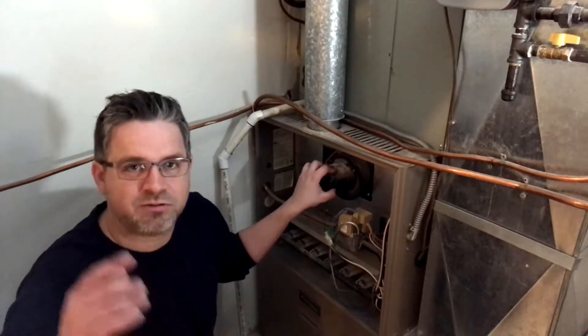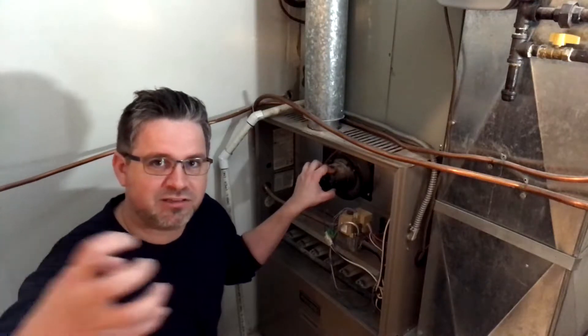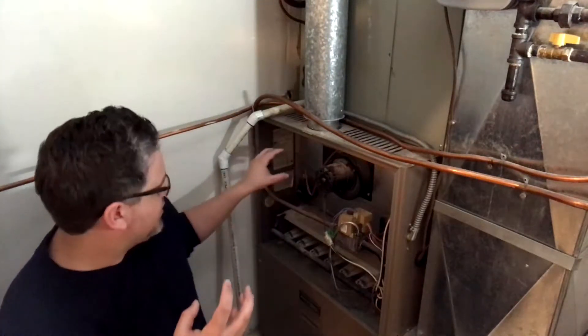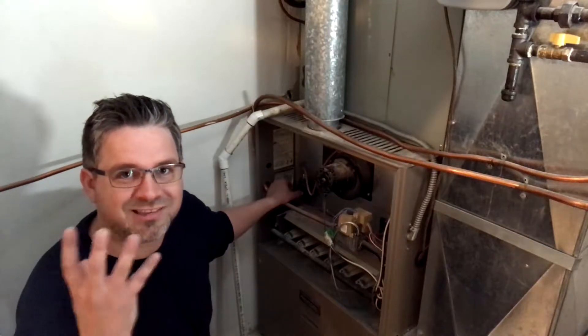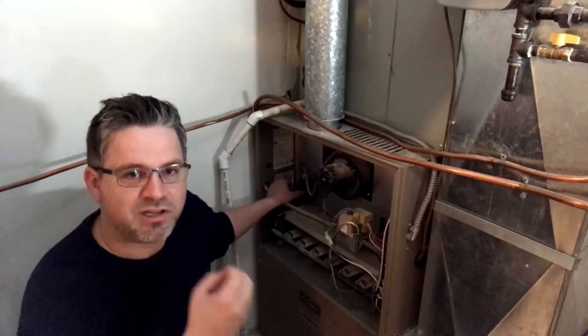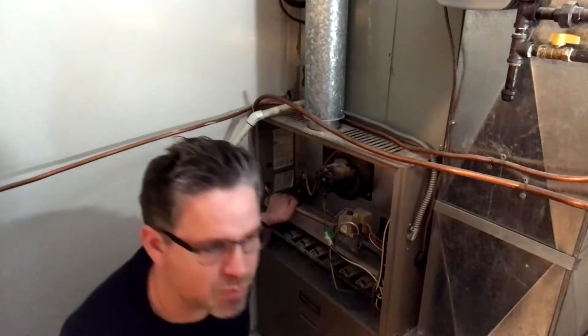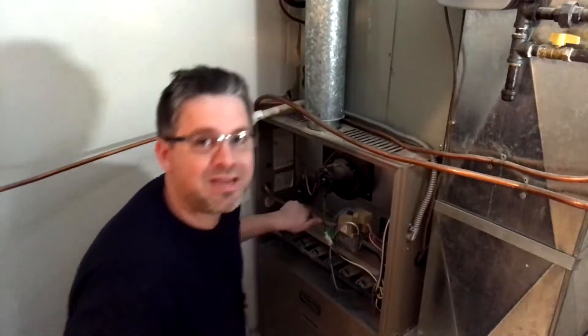To make sure that the inducer fan is running and that the exhaust gases are getting sucked out and leaving the furnace, there's a little part here called the pressure switch. It senses that that part's running. It's like a little double check. Going down one more step, this thing is called a gas valve.